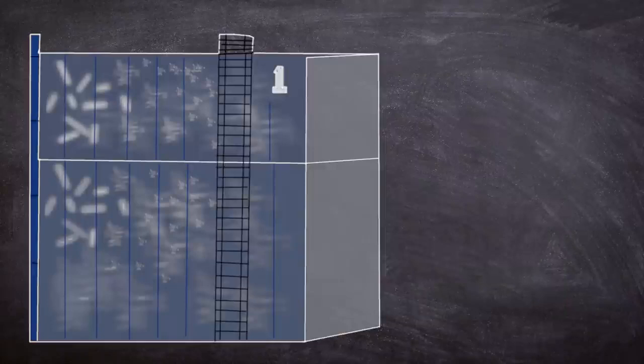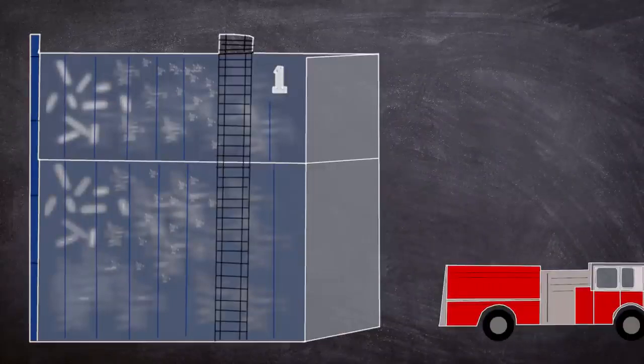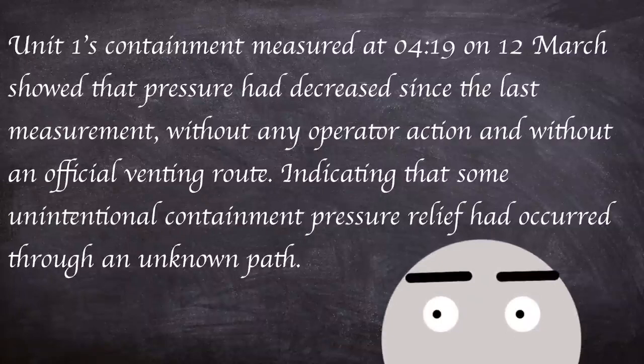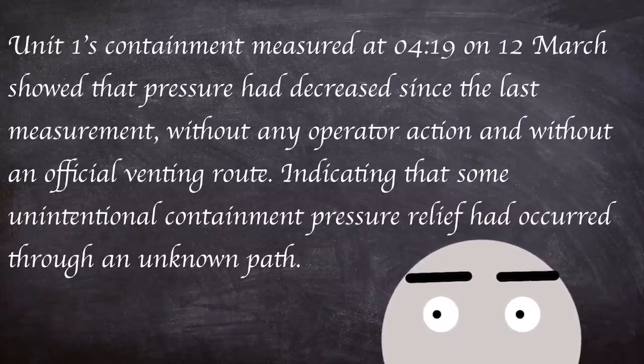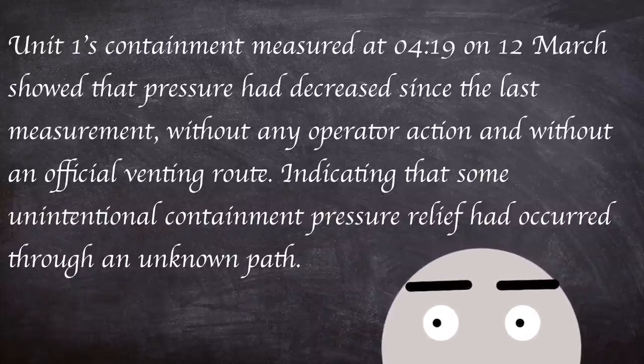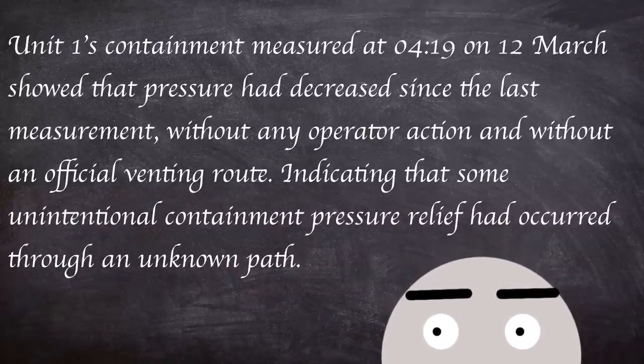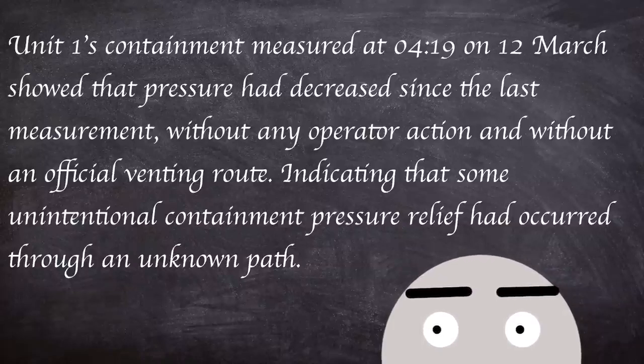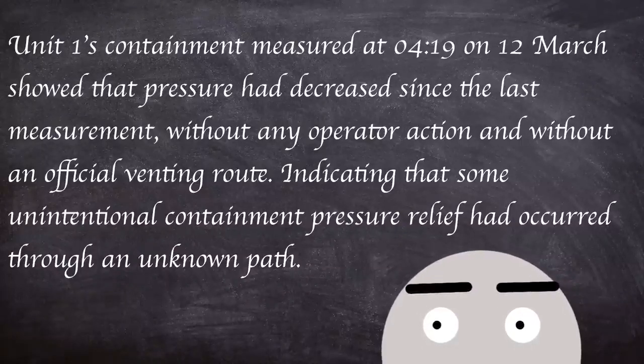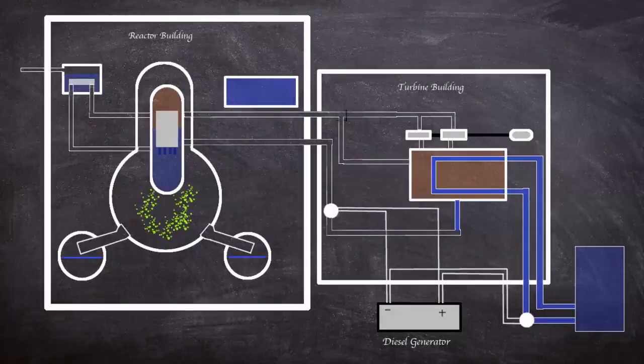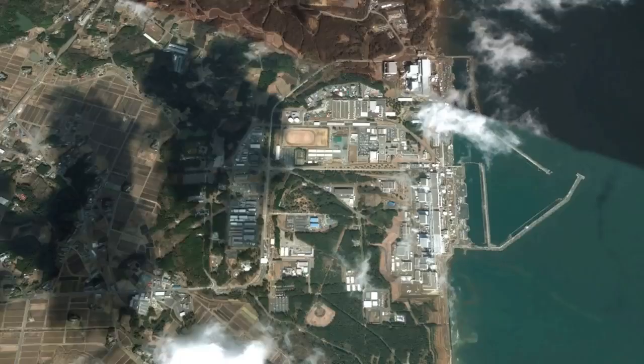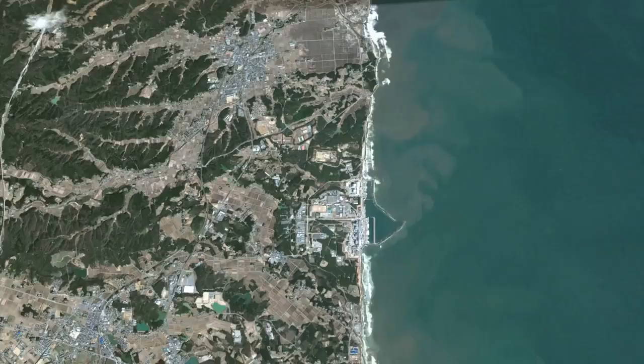At 4 am an alternate cooling system was put into operation, using firetrucks pumping seawater into unit 1 as the vessel pressure had reduced. Unit 1's containment measurement at 4:19 am on the 12th of march showed that pressure had decreased since the last measurement, without any operator action and without an official venting route, indicating that some unintentional containment pressure relief had occurred through an unknown path. This coupled with an increase in radiation levels hinted at reactor vessel damage. Because of this, the government extended the evacuation zone to 10 kilometers.